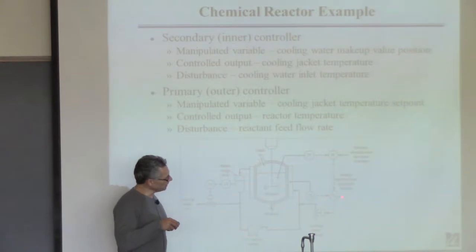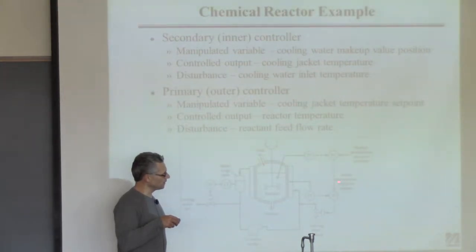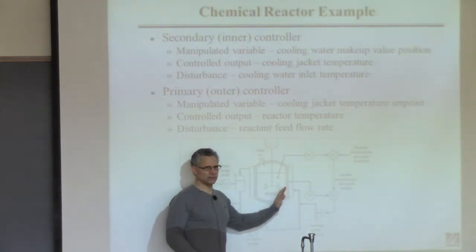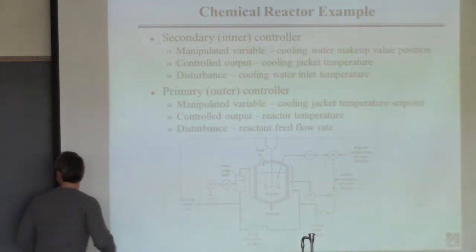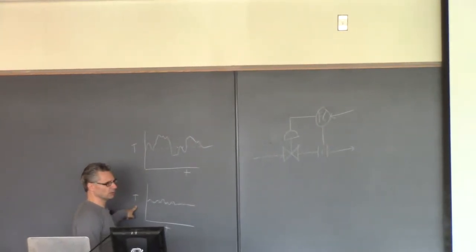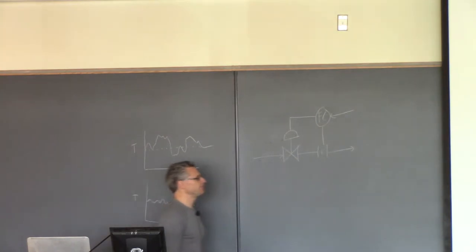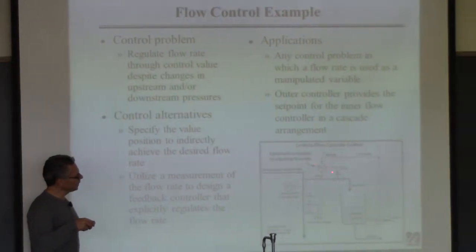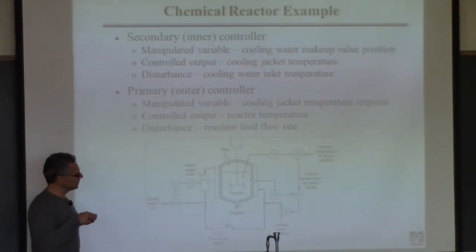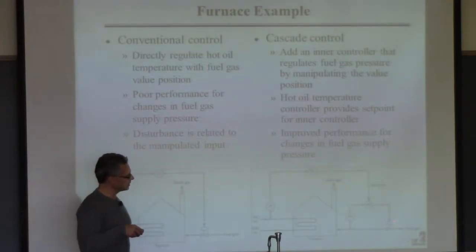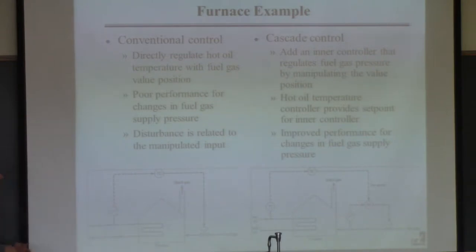So if this controller works to keep the temperature the same, and then this controller changes the target temperature — the set point — if this changes you'll see it much more quickly there and you can compensate for it right away. It'll reduce variability. And again, this one over here was a level-to-flow cascade, this one is a temperature-to-flow cascade, and the other one is essentially another temperature-to-flow cascade because I consider pressure of a gas to be the flow of the gas. So there are always valves and flows.